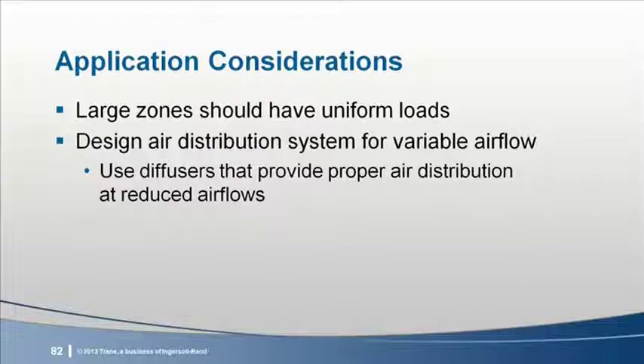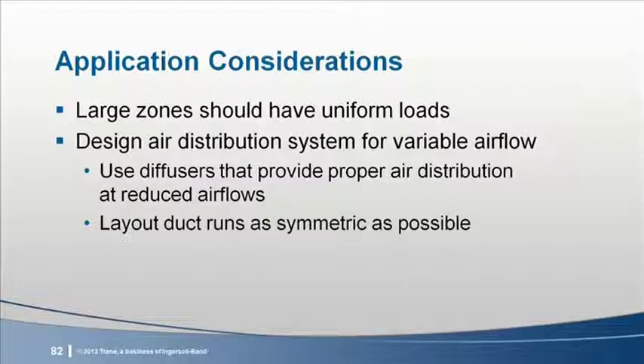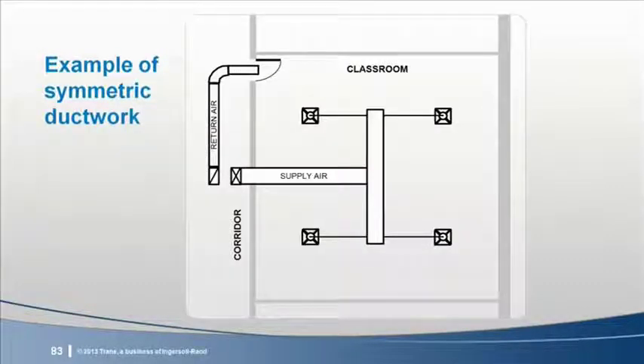Use diffusers that will provide proper air distribution at reduced airflows. Diffusers that are appropriate for conventional VAV systems are probably best suited. And, in general, keep the duct runs as short and symmetric as possible. Systems with longer or asymmetric duct runs are more susceptible to unequal airflows between diffusers as the supply fan modulates. Here's an example of symmetric ductwork. The path from the supply fan to each of the 4 diffusers is about the same, so pressure losses of the 4 paths are about equal. This is good practice for any air system.